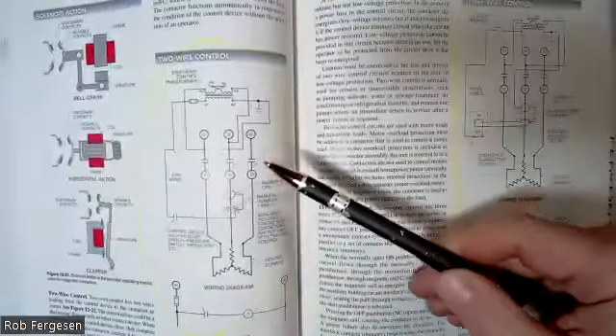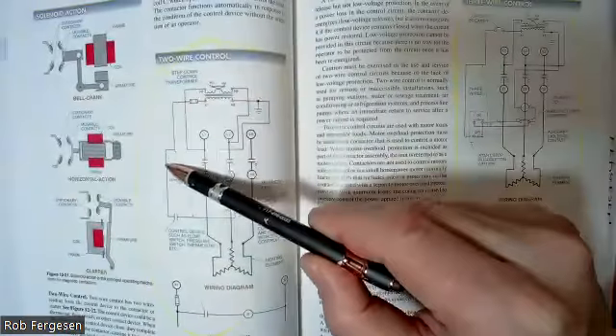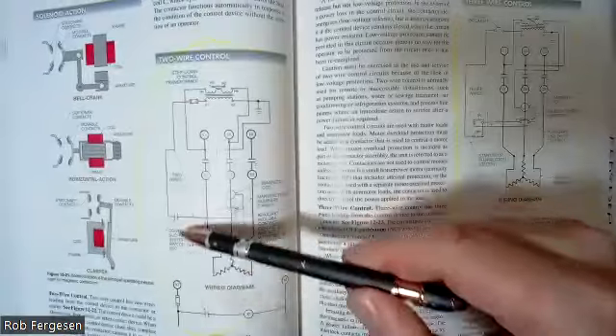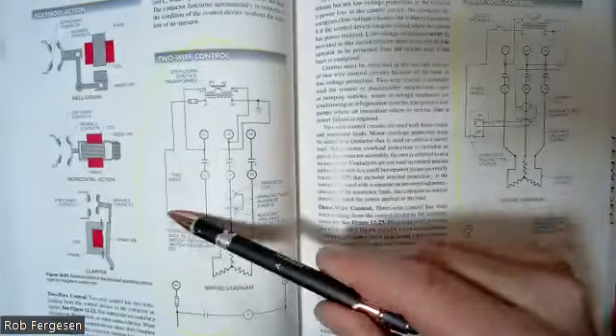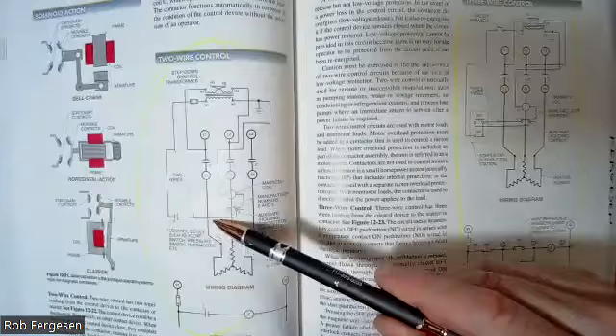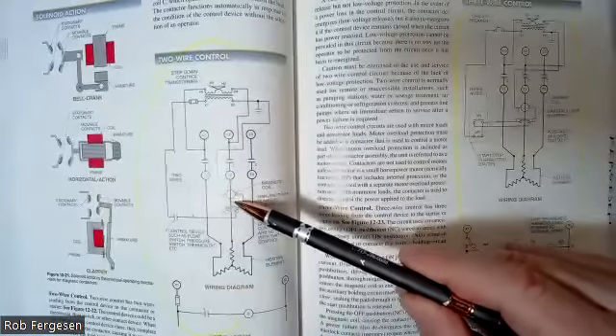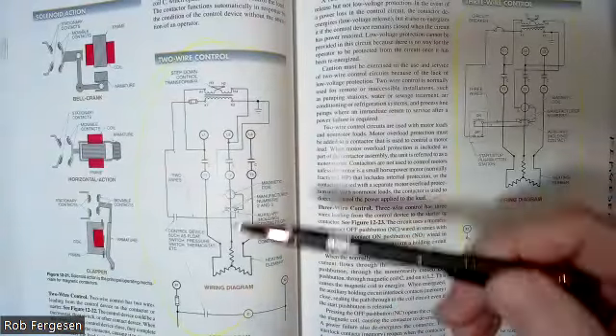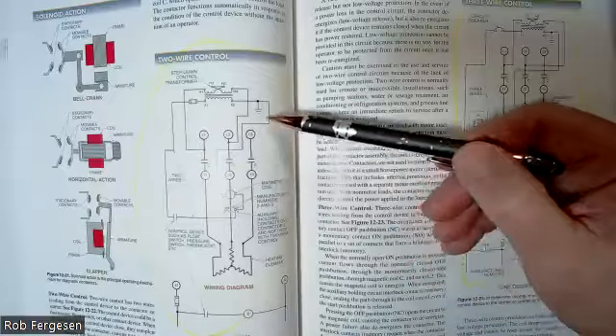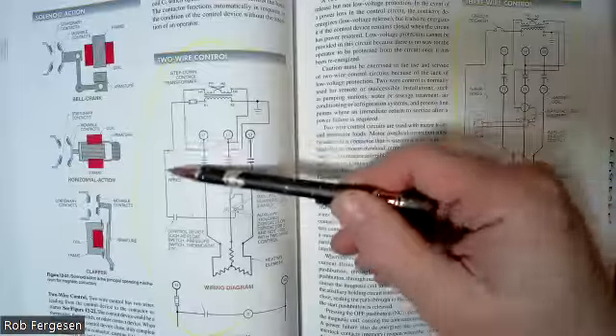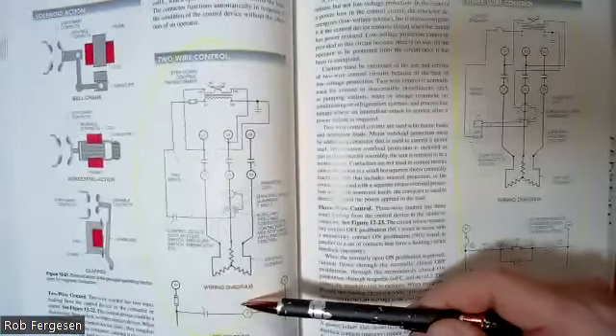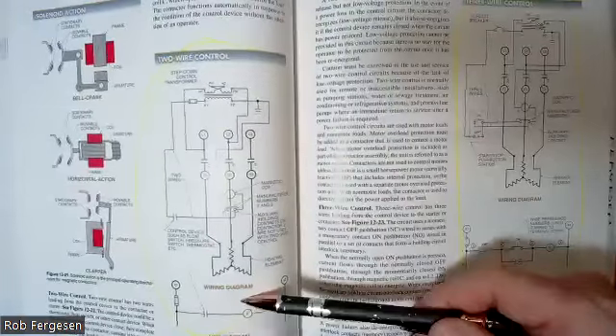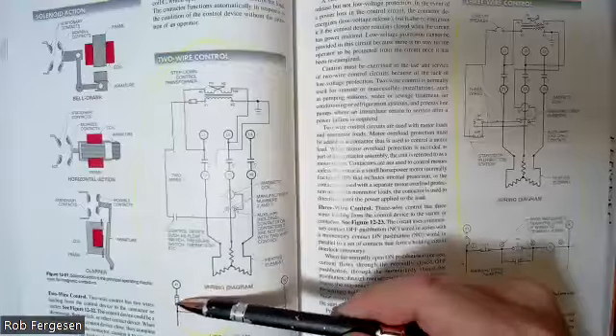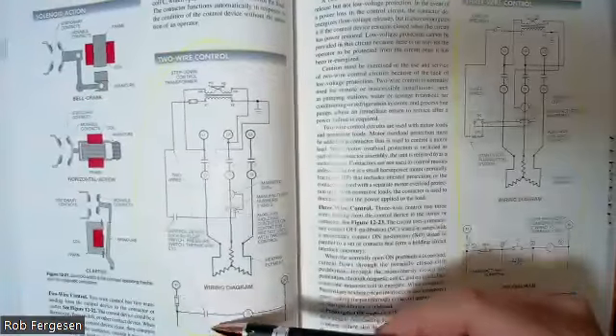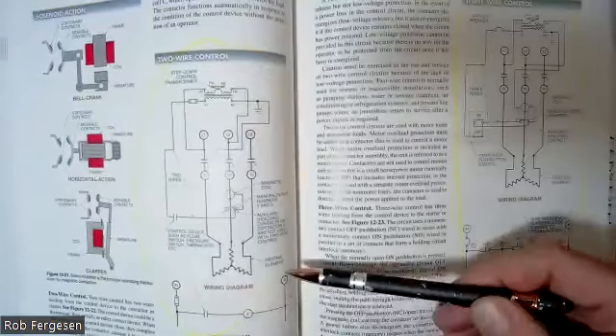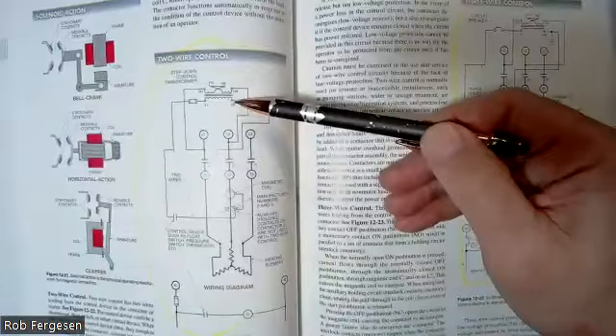They show you a little extra piece on here. They show you the wires that would go down that kind of duplicate. They show you that switch here, and they show you where that coil would be kind of here. I don't think it adds any value to show these wires extra up here. This is where you're typically going to see it on most diagrams. You're going to see a separate little line diagram, the fuse for your control power, the switch, the coil, and then the other control power connection X2.